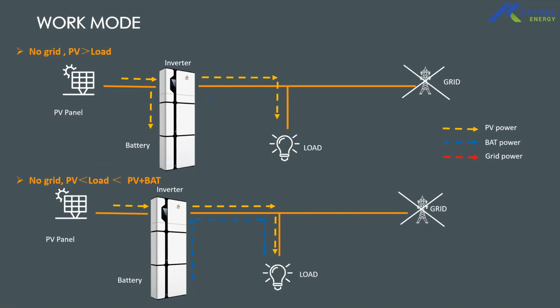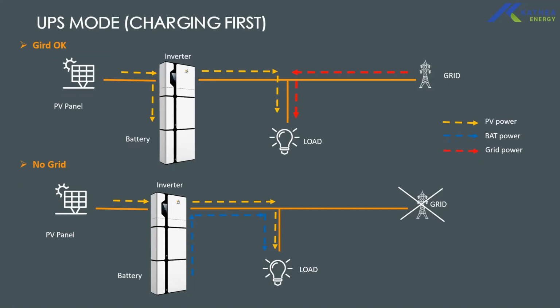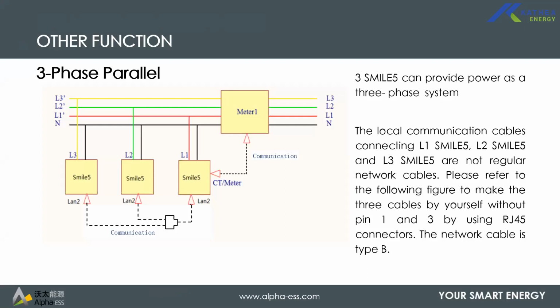So these are the different work modes. When you don't have grid and you have excess PV, the system will supply your loads and charge your battery. If you don't have grid, you can get your system to use PV and supplement your critical loads with the battery as well. And then you can actually set the system to charge from the grid. When it's charging from the grid, the system would use your PV to supply your loads, and then it will use the grid to charge your batteries. Or depending on the battery SOC, it can use the PV to charge your battery and supply your loads, and then the deficiency of the loads is supplied by the grid. So these are just different work mode scenarios.